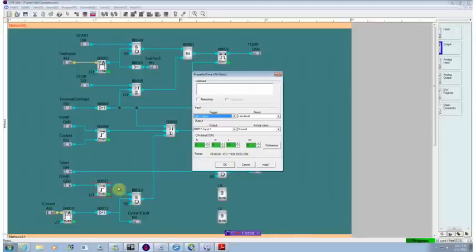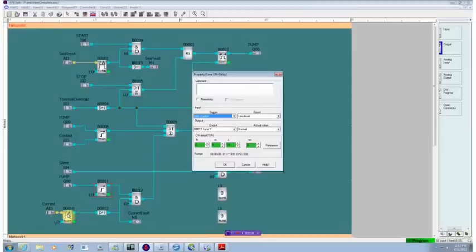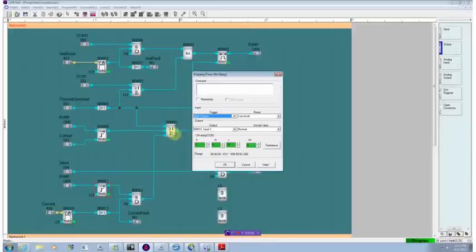So after ten seconds of the pump being on, then this output will go active. If this current hasn't been satisfied, this output will be active. Those two signals combine together to generate an alarm condition up here.